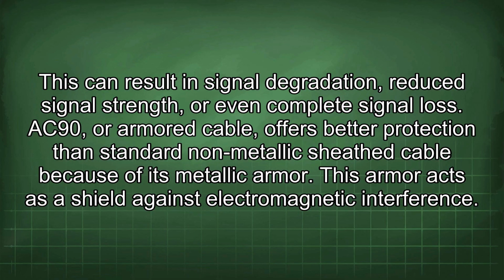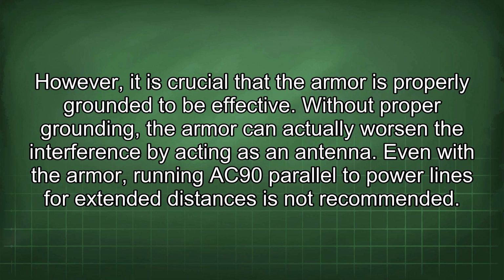A C90, or armored cable, offers better protection than standard non-metallic sheath cable because of its metallic armor. This armor acts as a shield against electromagnetic interference. However, it is crucial that the armor is properly grounded to be effective. Without proper grounding, the armor can actually worsen the interference by acting as an antenna.